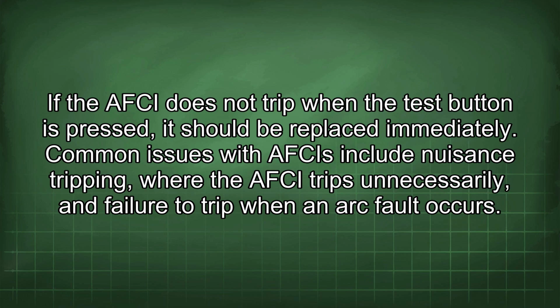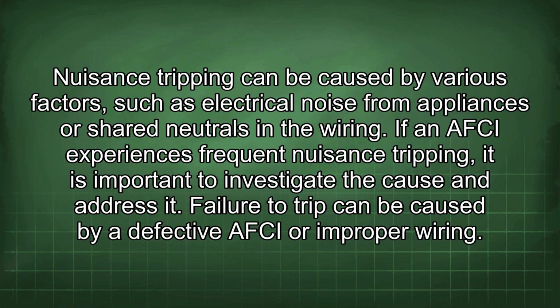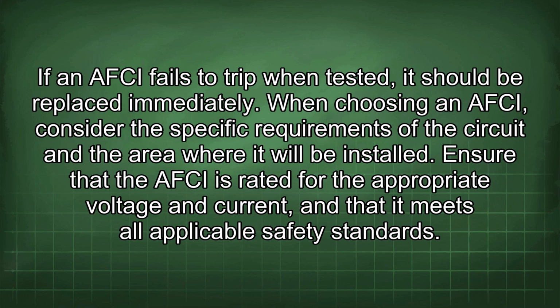Common issues with AFCIs include nuisance tripping, where the AFCI trips unnecessarily, and failure to trip when an arc fault occurs. Nuisance tripping can be caused by various factors, such as electrical noise from appliances or shared neutrals in the wiring. If an AFCI experiences frequent nuisance tripping, it is important to investigate the cause and address it. Failure to trip can be caused by a defective AFCI or improper wiring. If an AFCI fails to trip when tested, it should be replaced immediately.